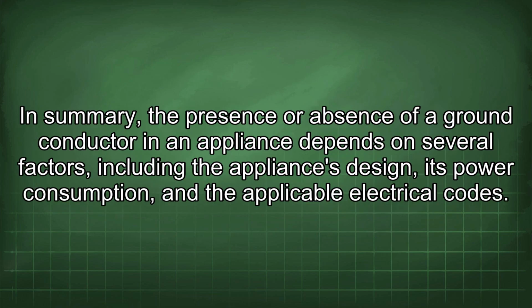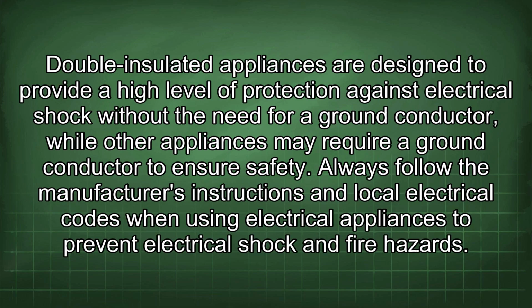In summary, the presence or absence of a ground conductor in an appliance depends on several factors, including the appliance's design, its power consumption, and the applicable electrical codes. Double-insulated appliances are designed to provide a high level of protection against electrical shock without the need for a ground conductor, while other appliances may require a ground conductor to ensure safety. Always follow the manufacturer's instructions and local electrical codes when using electrical appliances to prevent electrical shock and fire hazards.